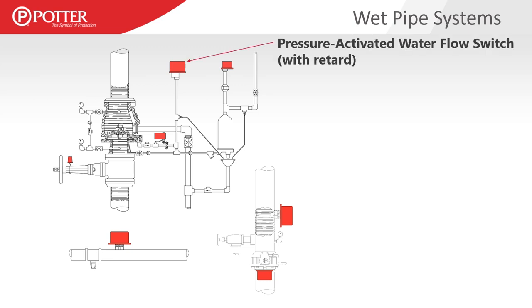Some of the different types of electronic devices we're going to address today include a pressure-activated water flow switch — in this case, a pressure switch with a built-in retard that allows the pressure to fluctuate throughout the day of a normal wet pipe system without activating the alarm. You also have pressure switch-based water flow switches that don't have a built-in retard, which would sit on top of a retard chamber to absorb those fluctuations.